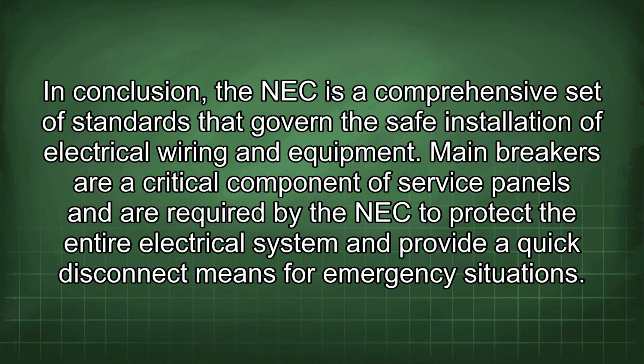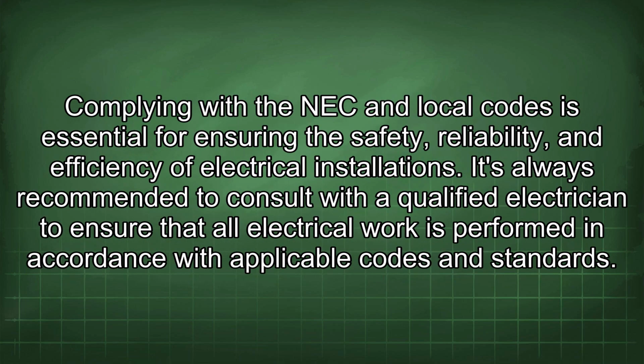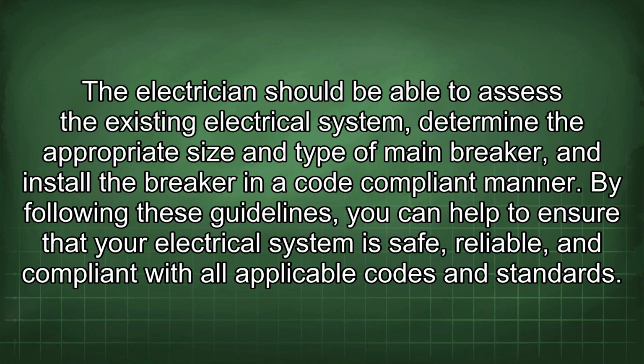Main breakers are a critical component of service panels and are required by the NEC to protect the entire electrical system and provide a quick disconnect means for emergency situations. Complying with the NEC and local codes is essential for ensuring the safety, reliability, and efficiency of electrical installations. It's always recommended to consult with a qualified electrician to ensure that all electrical work is performed in accordance with applicable codes and standards. The electrician should be able to assess the existing electrical system, determine the appropriate size and type of main breaker, and install the breaker in a code-compliant manner.